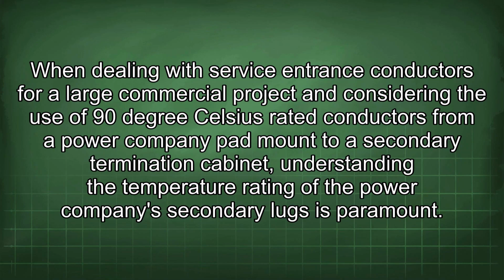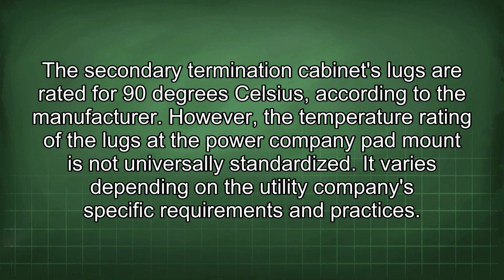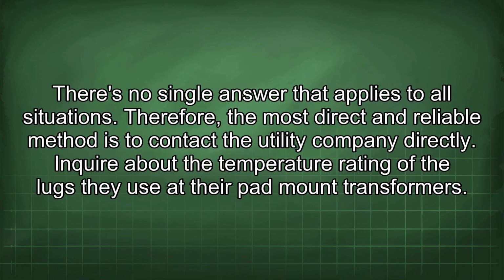When dealing with service entrance conductors for a large commercial project and considering the use of 90°C rated conductors from a power company pad mount to a secondary termination cabinet, understanding the temperature rating of the power company's secondary lugs is paramount. The secondary termination cabinet's lugs are rated for 90°C according to the manufacturer. However, the temperature rating of the lugs at the power company pad mount is not universally standardized. It varies depending on the utility company's specific requirements and practices. There's no single answer that applies to all situations.